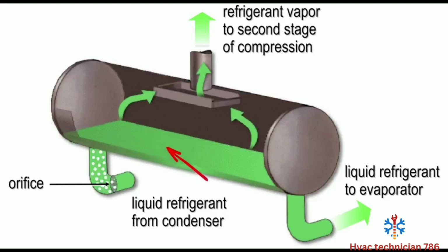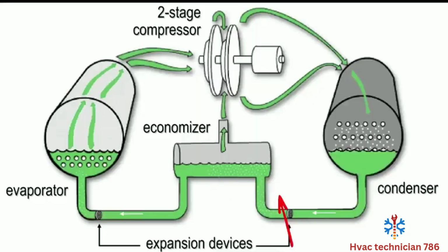Our liquid from the flash is going to stay here at the bottom and collect, and our flash gas is going to flow. It's going to hit in between our first and second stage. Coming up to this example, we can see our refrigerant path. We come down our condenser through the orifice plate and into this economizer. As the flash gas pulls up in between these, it's an interstage suction that's pulling in, meaning that we don't have to pull all of our refrigerant through the full stages of the compressor.